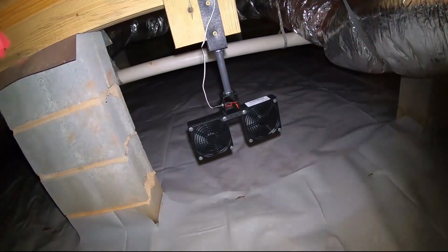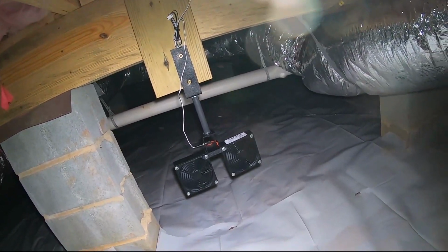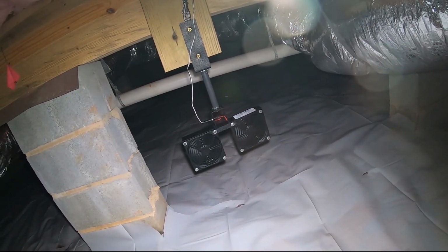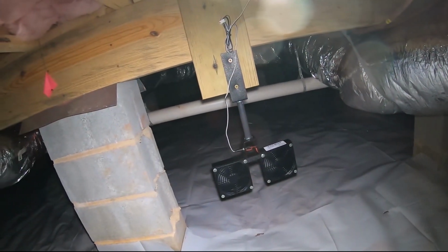As we can see here, we have a dead corner fan. It is running right now. The Atmox system works on a dew point fired premise. So instead of running the dehumidifier all the time, we're able to utilize the outside air when it's drier outside. Of course, being a summer day, we cannot use the outside air, so we are on the internal fans. And also, we'll show you here today, we've deployed a commercial dehumidifier as a backup program to this Atmox system.